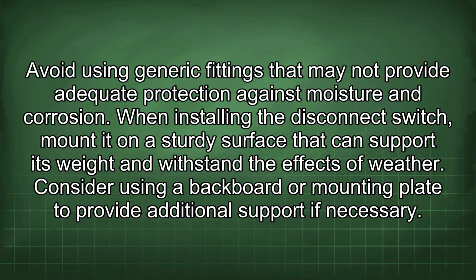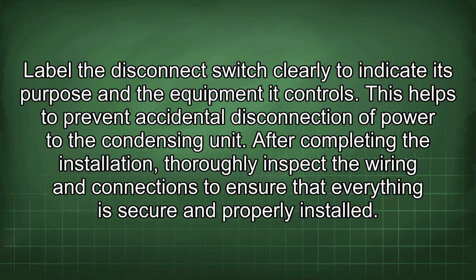When installing the disconnect switch, mount it on a sturdy surface that can support its weight and withstand the effects of weather. Consider using a backboard or mounting plate to provide additional support if necessary. Label the disconnect switch clearly to indicate its purpose and the equipment it controls. This helps to prevent accidental disconnection of power to the condensing unit.